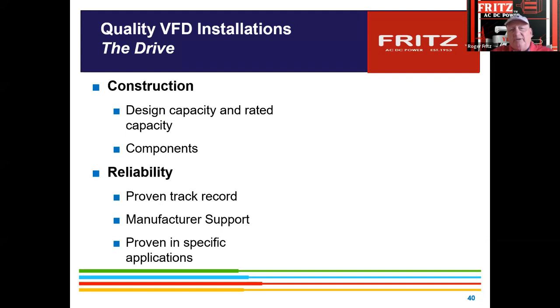You want to look at the construction of the capacitors. We don't sell variable torque drives. What a variable torque drive actually is, is a constant torque drive, meaning 150% overload for 1 minute, derated to 125%. So they're able to put that on a 100 horsepower drive. They can put it on a 125 horsepower motor on a fan or pump.